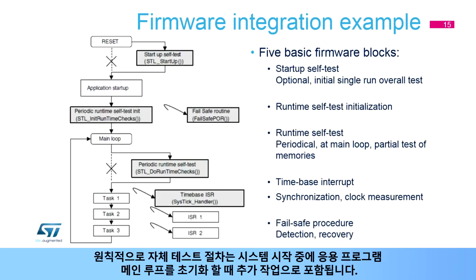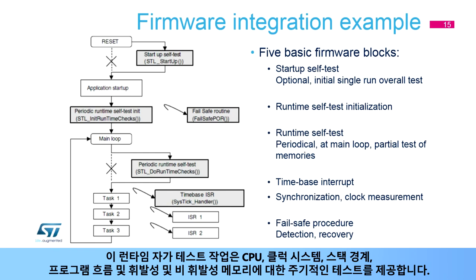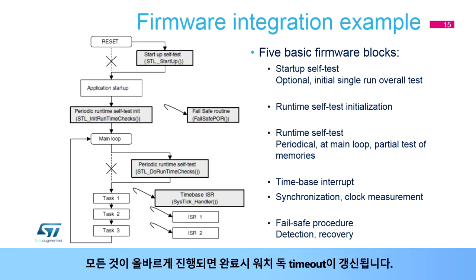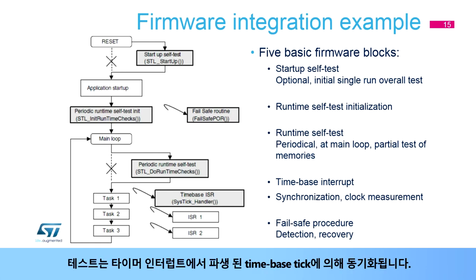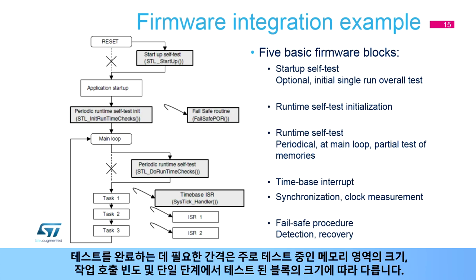In principle, self-test procedures are included as an additional task when initializing the application main loop during system startup. This runtime self-test task provides periodic testing of the CPU, clock system, stack boundary, program flow, and both volatile and non-volatile memories. The watchdog timeout is refreshed upon completion if everything goes correctly. The memory areas are tested step-by-step per parts within the task, synchronized by time-based ticks derived from timer interrupts. The interval required to complete the test depends mainly on the size of the memory areas under test, the frequency of task calls, and the sizes of the blocks tested in a single step.